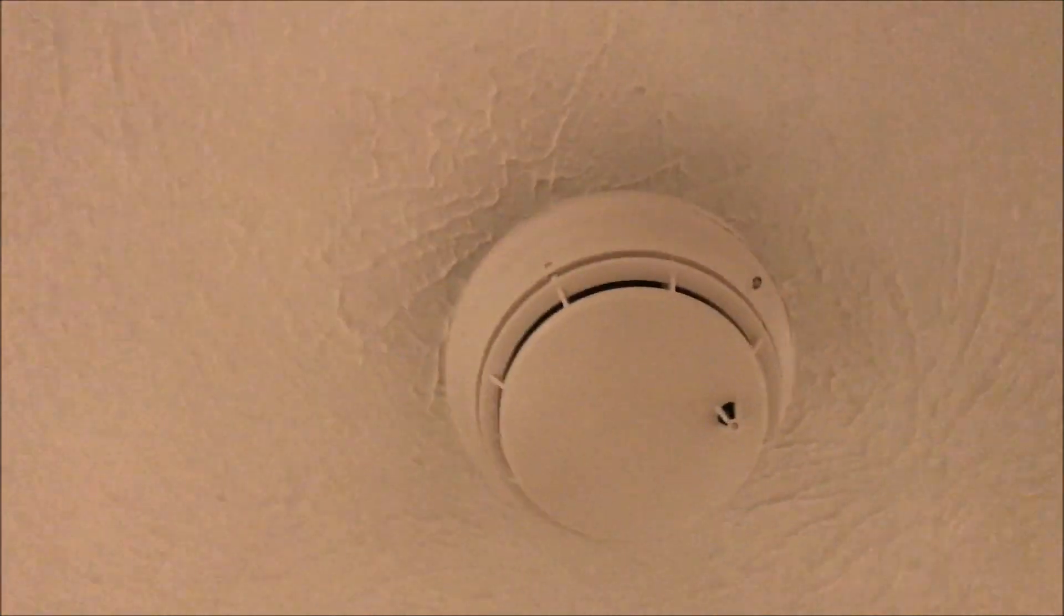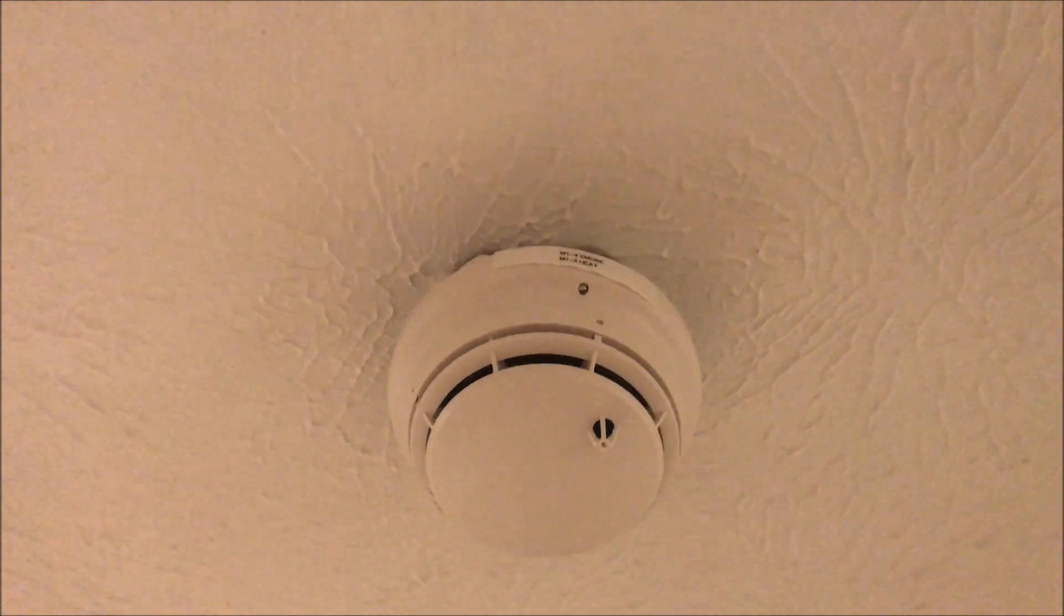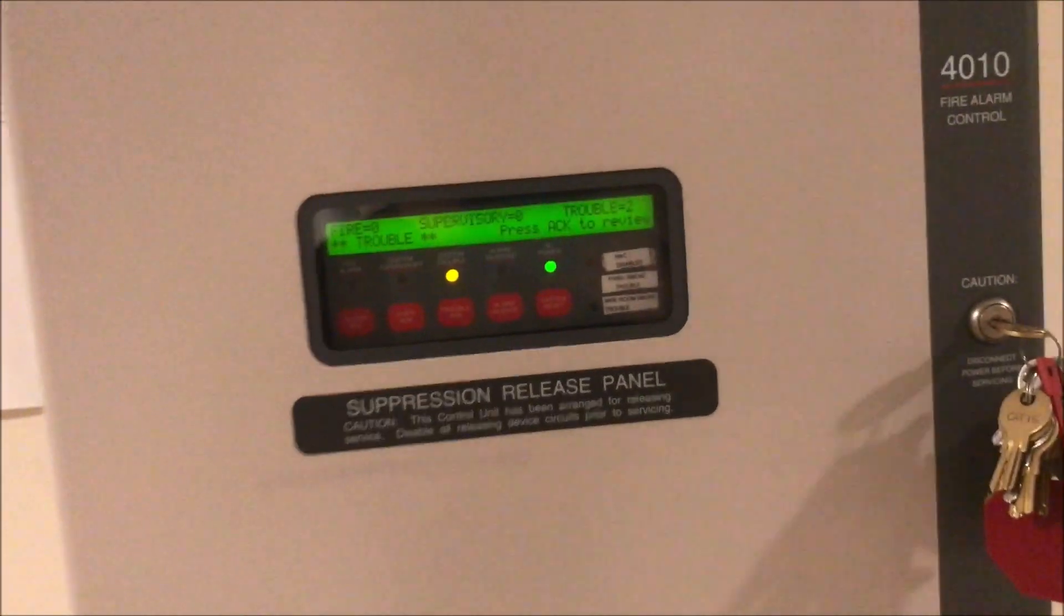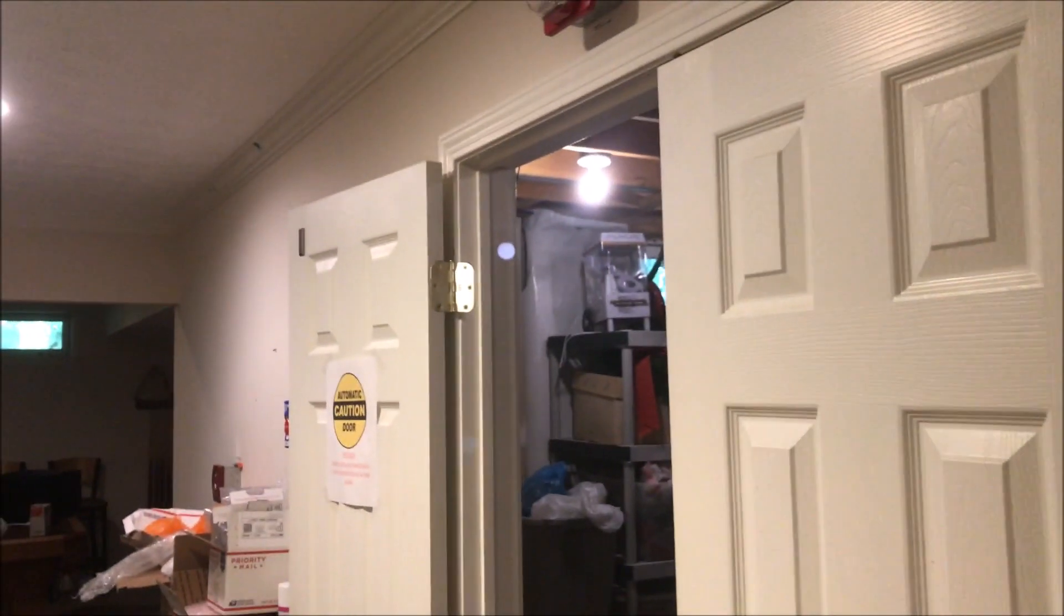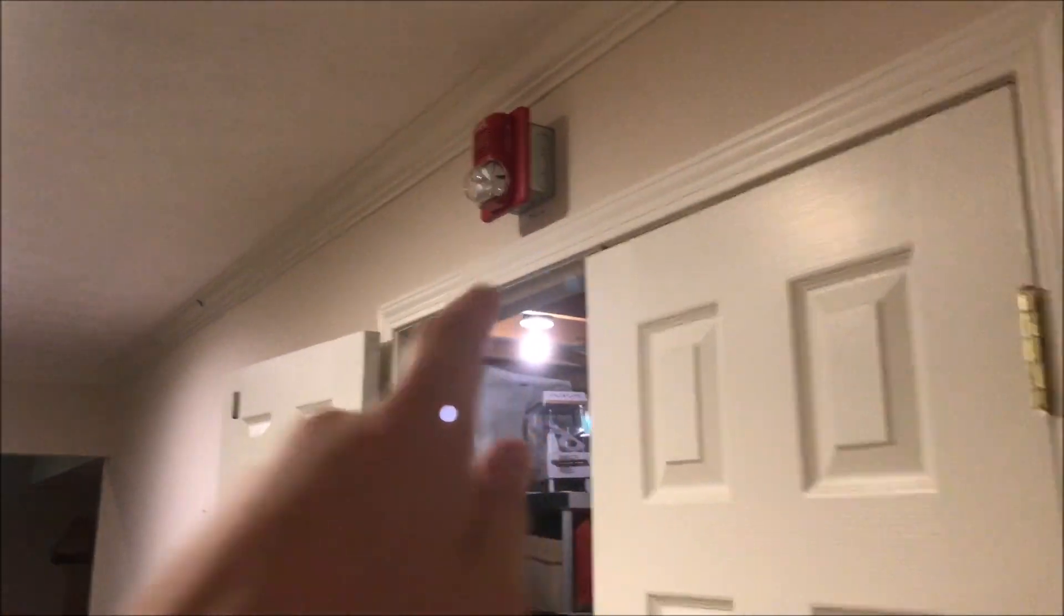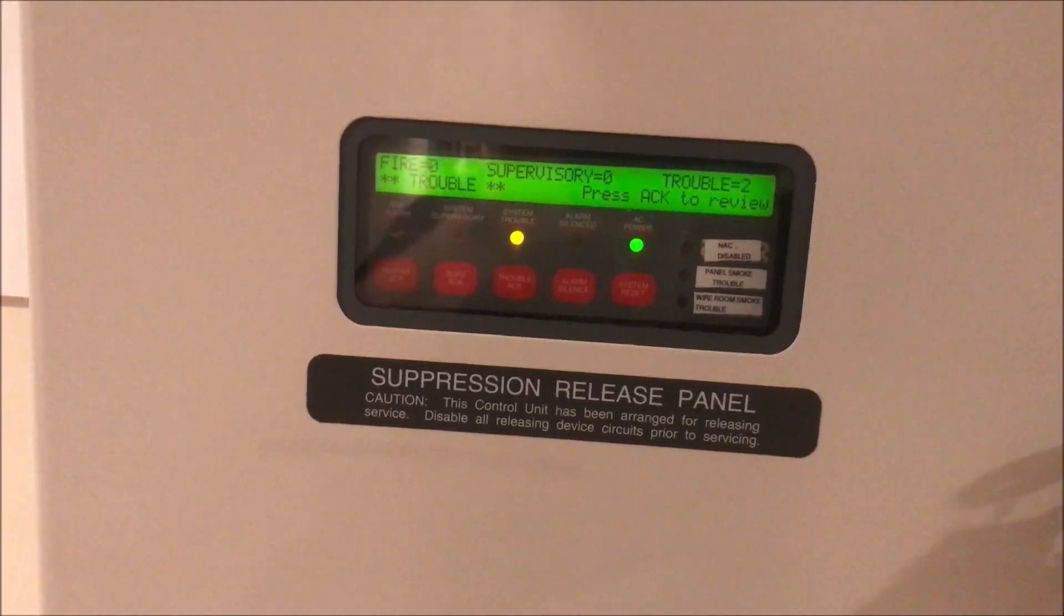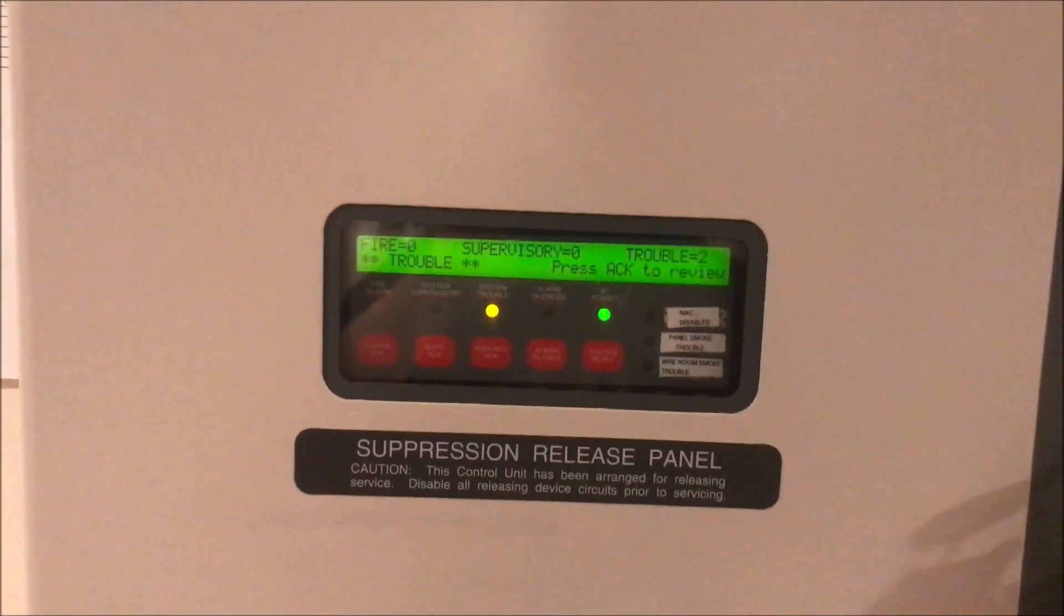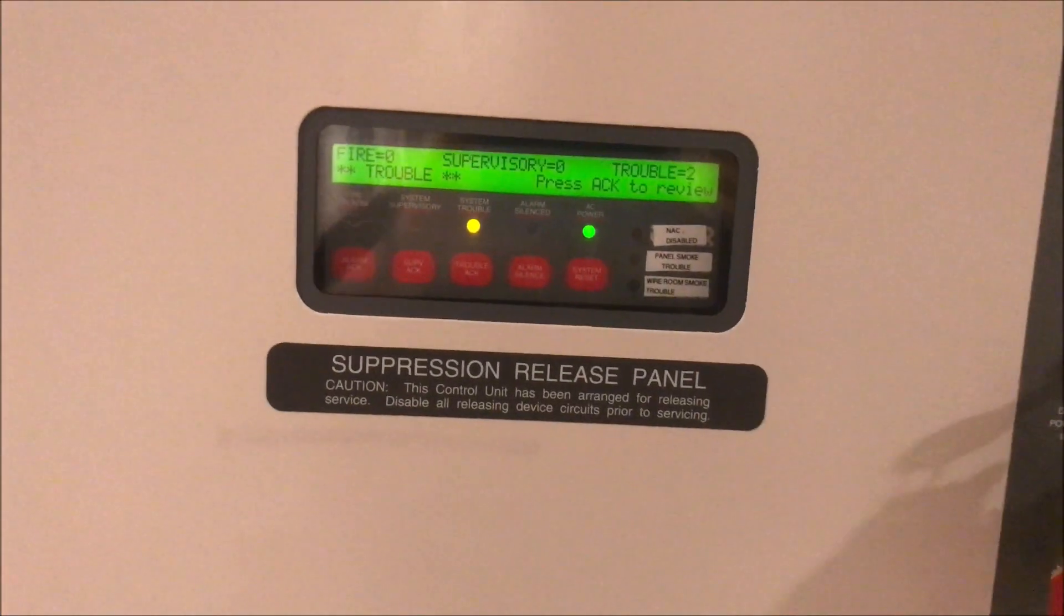That is address 0.5 on my panel. There are two troubles on my panel right now because I have the door holder and my visual circuit disabled through my panel, because we're going to be setting a lot of things off. It's just kind of a pain with a lot of strobes, frankly, but I am leaving this horn strobe operational.